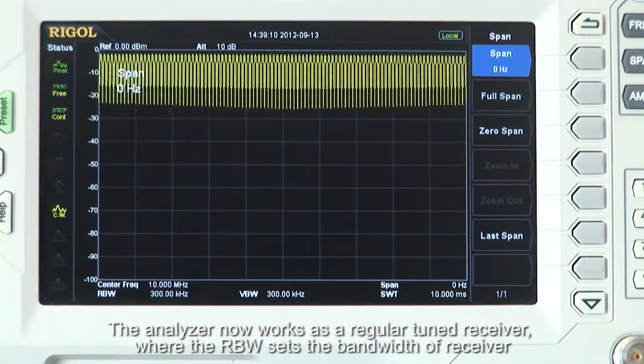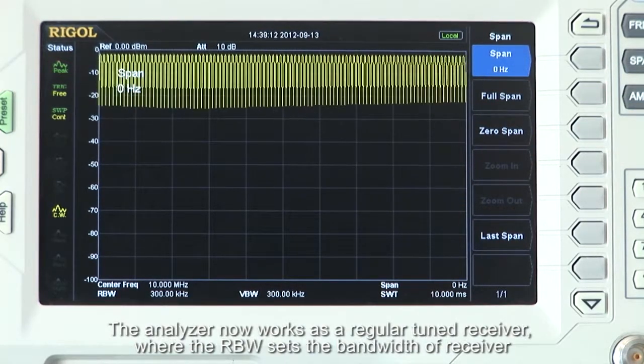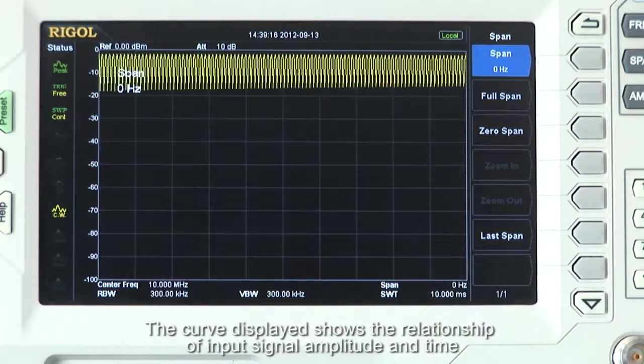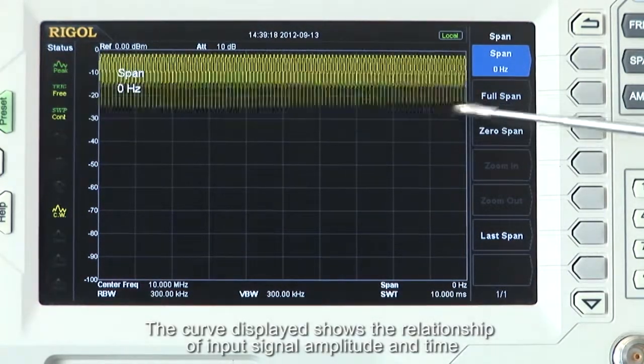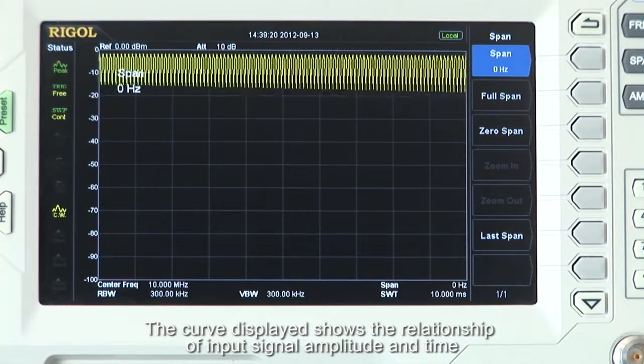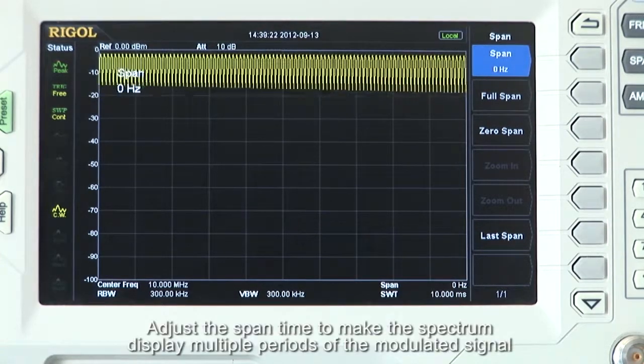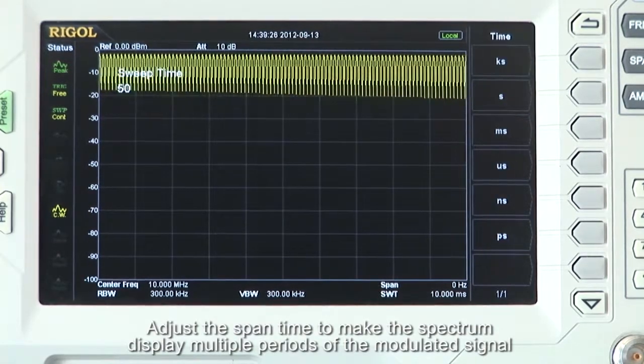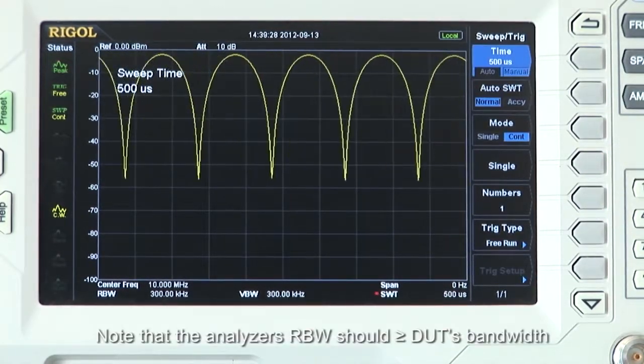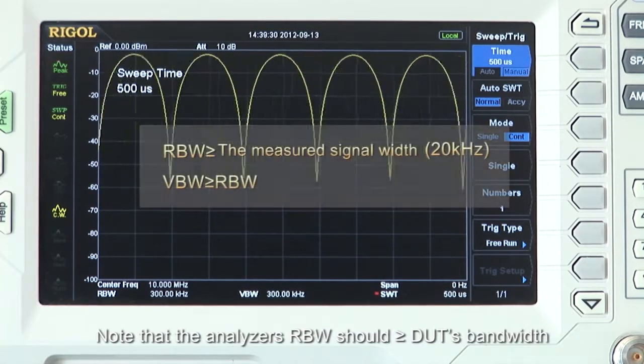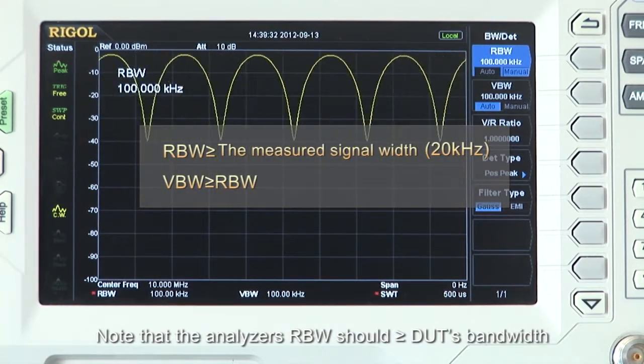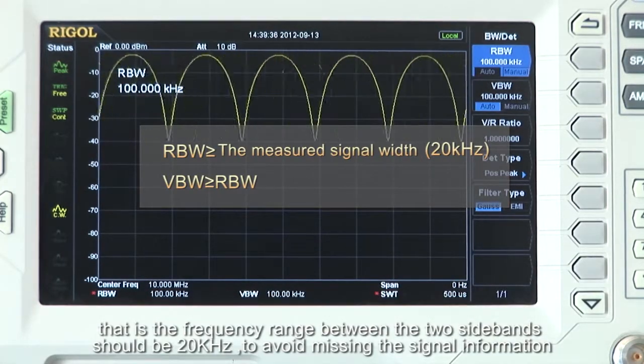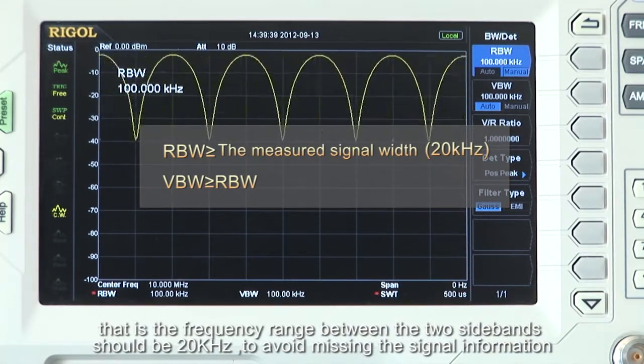The analyzer now works as a regular tuned receiver where the resolution bandwidth, or RBW, sets the bandwidth of the receiver. The curve displayed shows the relationship of input signal amplitude and time. Adjust the sweep time to display multiple periods of the modulated signal. Note that the analyzer's resolution bandwidth should be greater than or equal to the DUT's bandwidth — that is, the frequency range between the two sidebands — and it should be at least 20 kHz to avoid missing signal information.